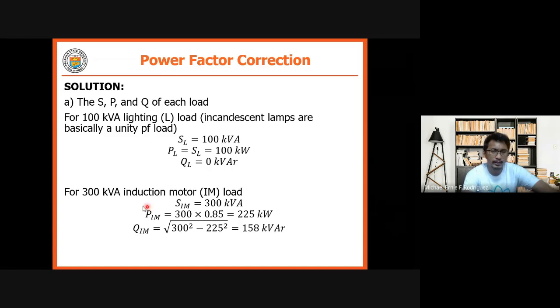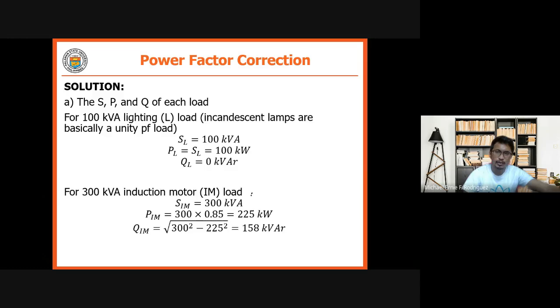Therefore, QL is 0. Next, for a 300 kVA induction motor load, IM. First, SIM, given yan 300 kVA. At yung power factor—0.85 yung PF. Yung relationship natin for P, from your circuits, is your S times your PF. Kaya nangyari, PIM is equal to 300 times 0.85, so this is now equal to 225 kilowatts.